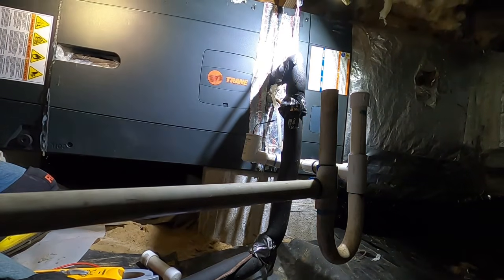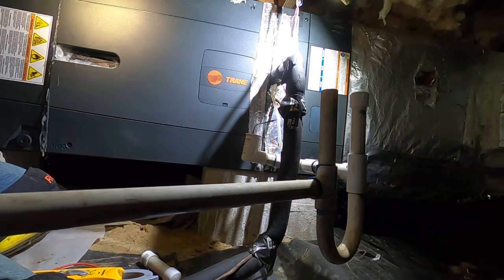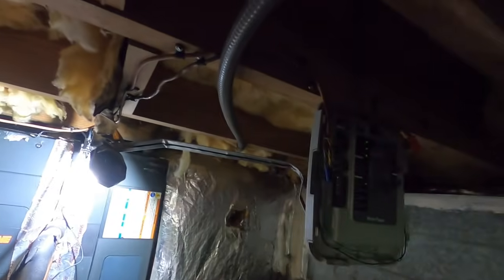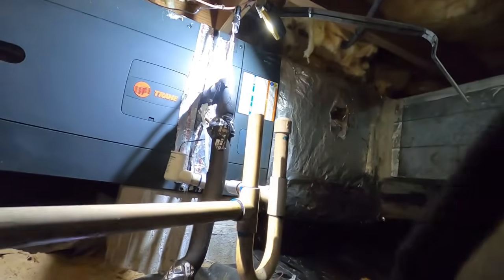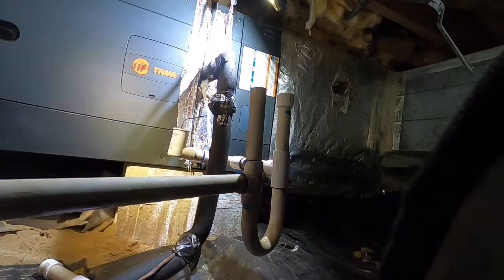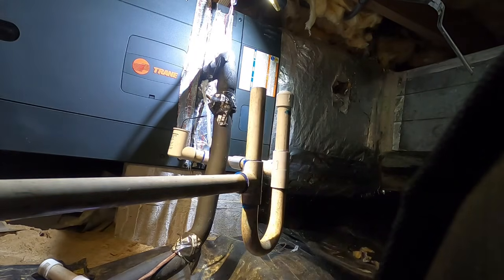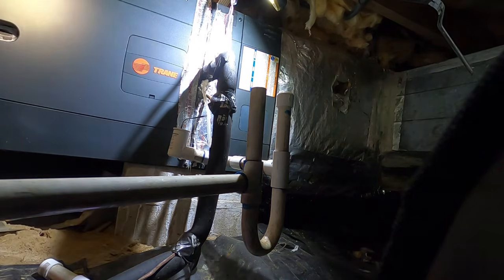Now this is a TAM. This is a TAM 7, and we got an 850 thermostat inside, and we've got a relay panel mounted right up here. So the thermostat communicates with that relay panel, and then that relay panel turns on the unit. 24 volts on this side, communicating on the thermostat side.